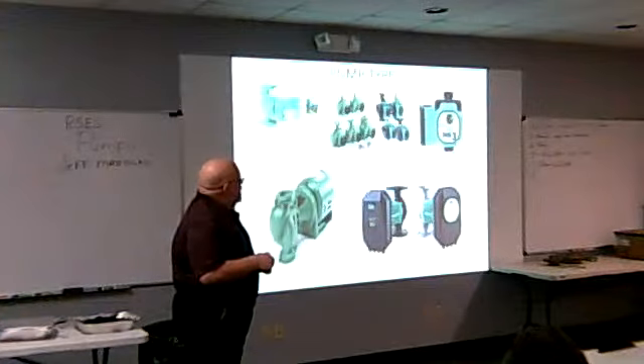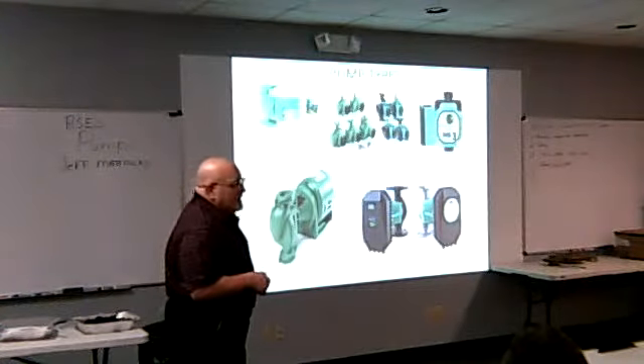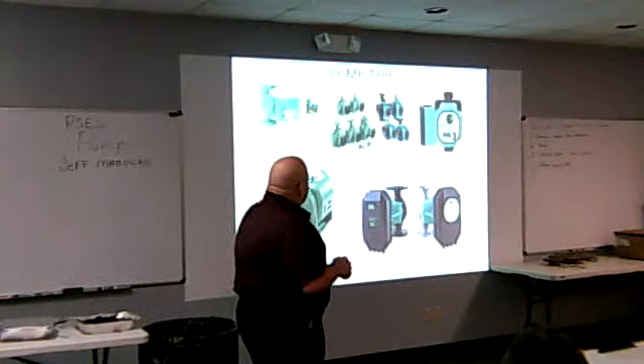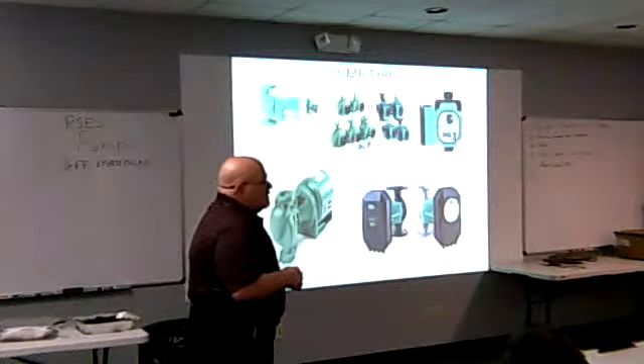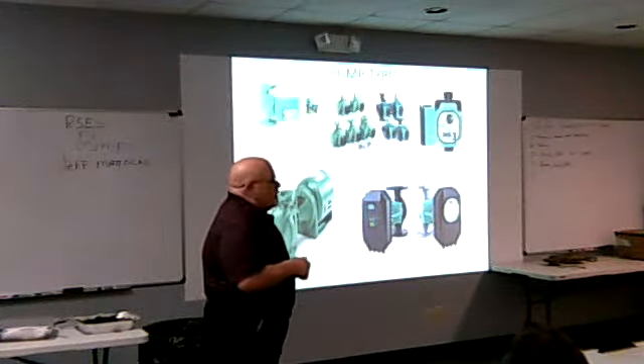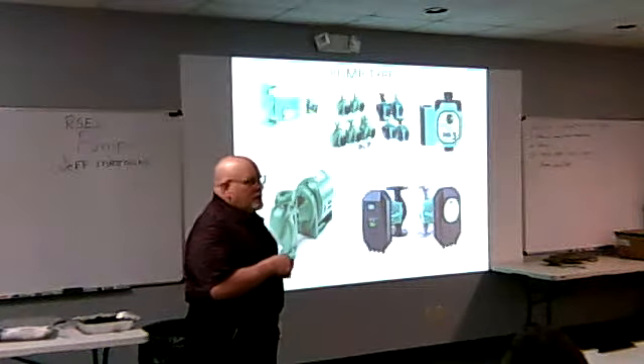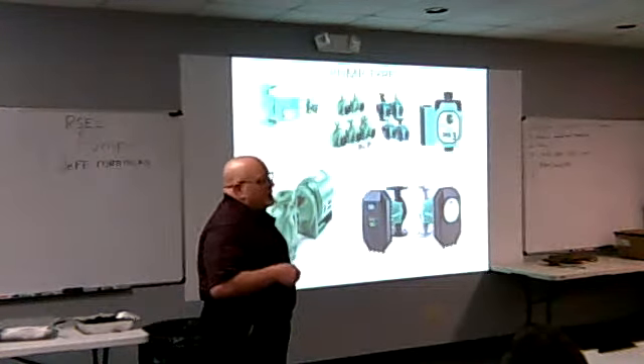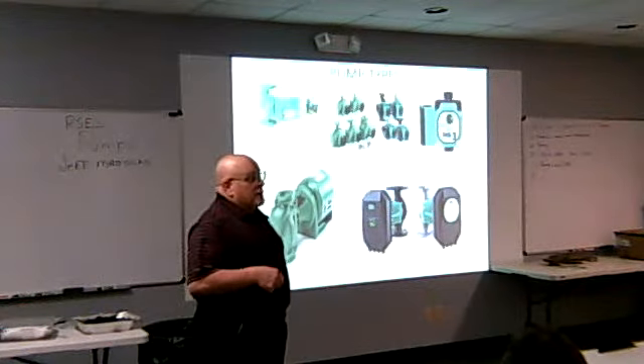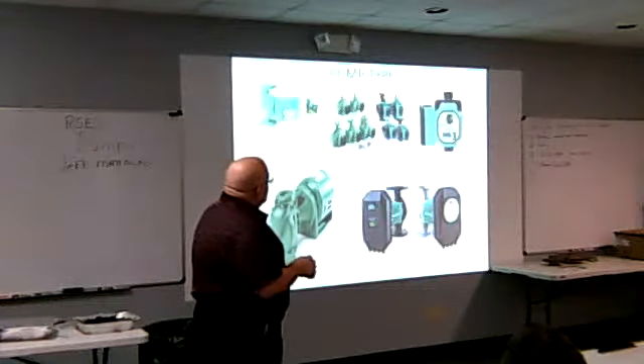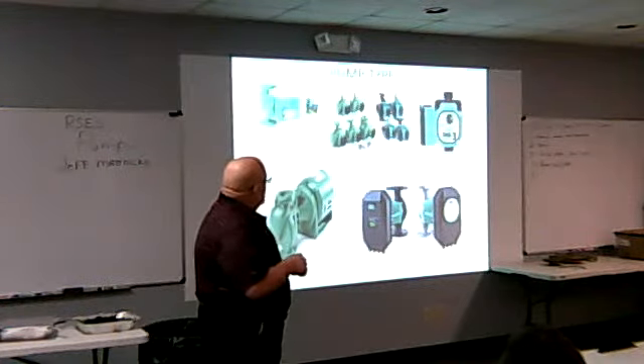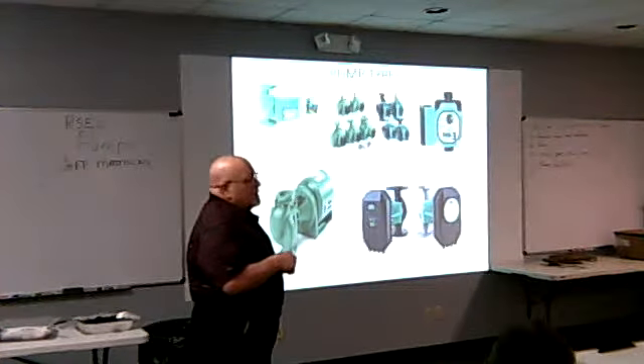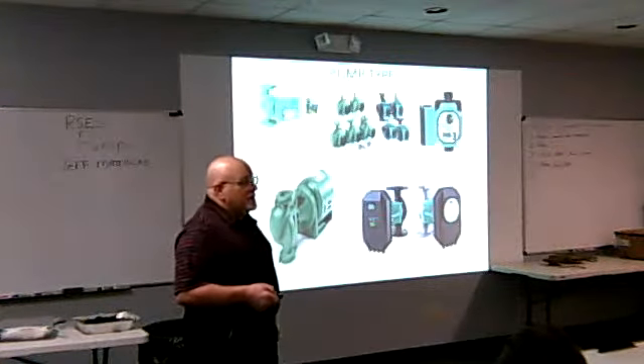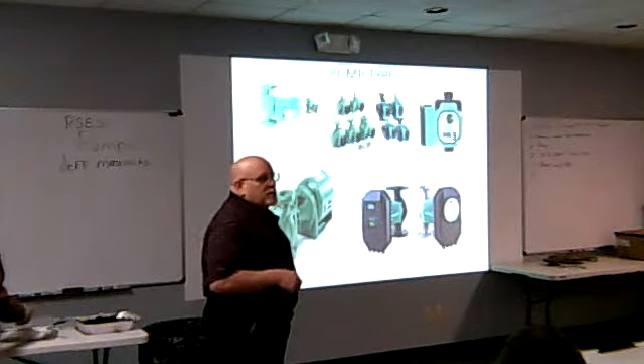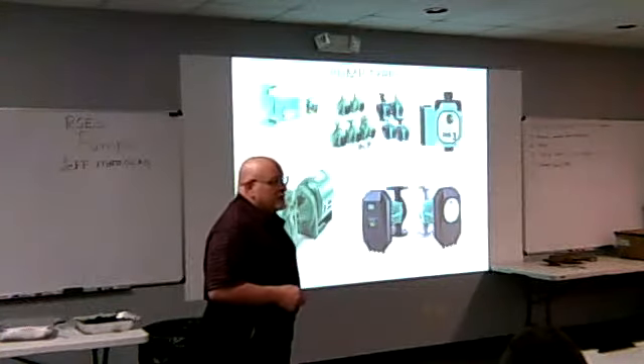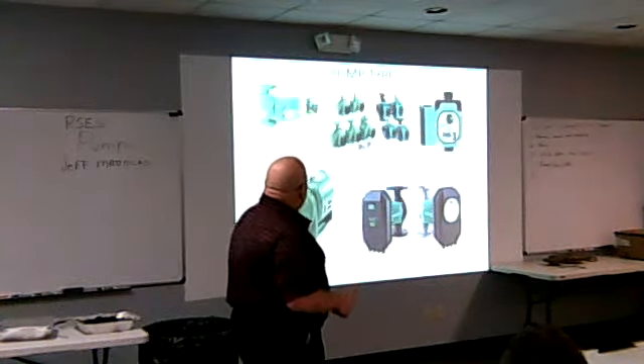Now there's a big change. These are 006Es. Everybody's going to ECM now, which is basically instead of having a wound synchronous motor, you now have a permanent magnet built into them. And a lot of times when you see these now, people are having to put a magnetic separator into their system. The reason is that this has a full magnet charge. When these shut off, the magnetism goes away. These are always magnetized. If you have any metal in the system, that's what they want to collect in your pumps. But now we're seeing a lot of magnetic separators being sold in addition to air separators.